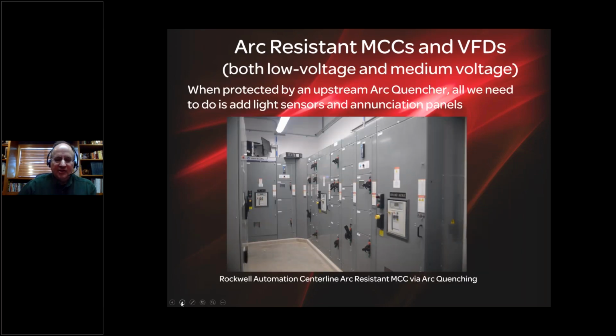So this is a picture of a Rockwell Centerline motor control center. It was constructed by Rockwell, not arc resistant. So this is a standard Centerline Series 2100 motor control center. This particular MCC is in a wastewater treatment plant that specified C37.20.7, but you can see there are no plenums up on top. There's no mechanical venting here whatsoever.